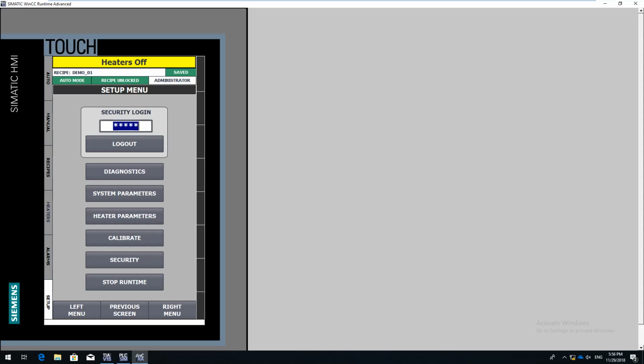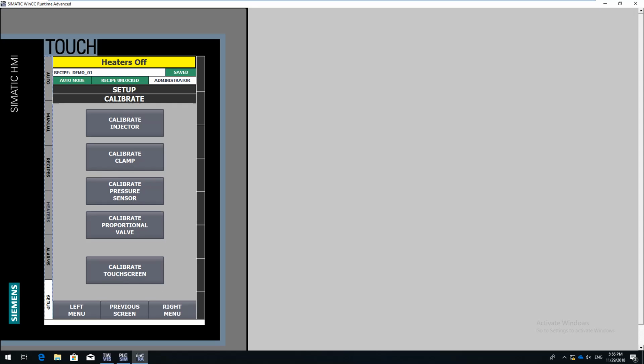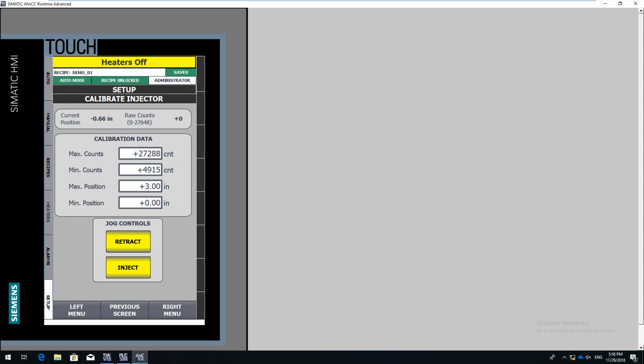Another option under Setup is Calibrate. This is used to calibrate the position for our injector, our clamp. We also have a pressure sensor on the hydraulic manifold, and we also have the proportional valve, which is how the PLC controls pressure in the manifold. So calibrating the injector and the clamp is not very difficult.